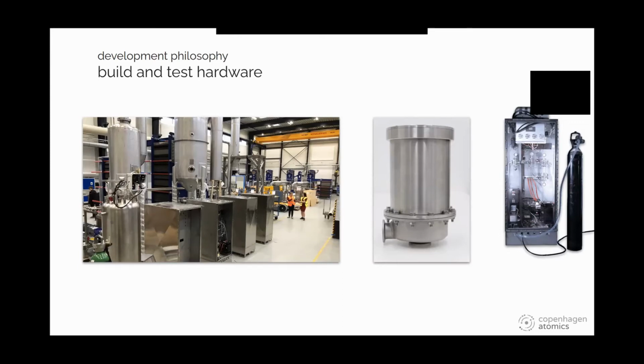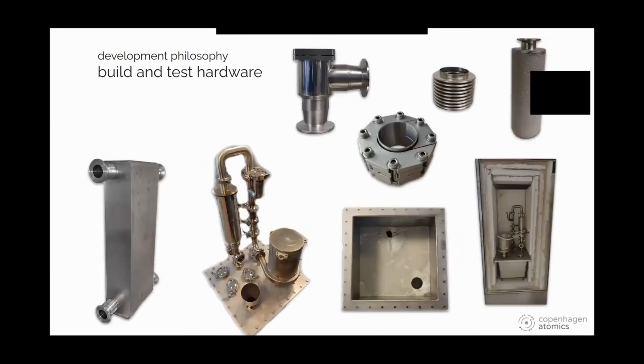And we're currently looking at building a version of this with electromagnetic bearings, which allows us to also levitate the impeller and rotor assembly on an electromagnetic field, so we don't have any wearing surfaces. With that, we expect to get something like 10 years lifetime inside our reactor without any maintenance or service, because there's no contact area besides the salt. And yeah, so this is what we're doing.